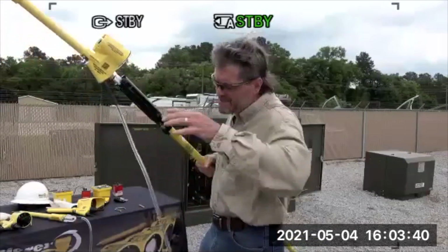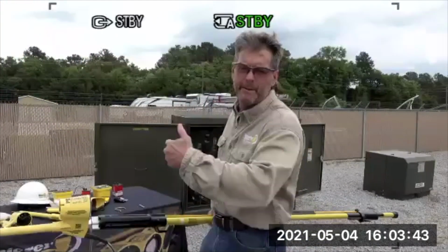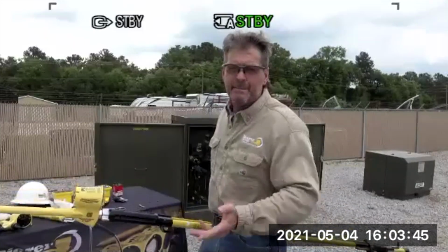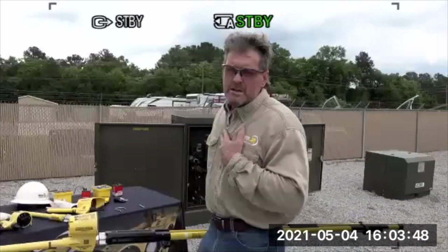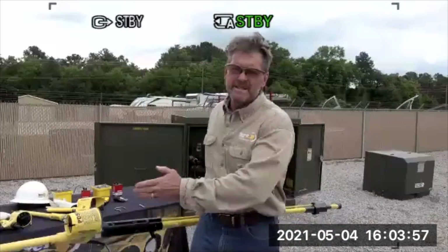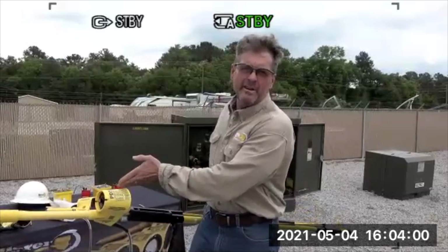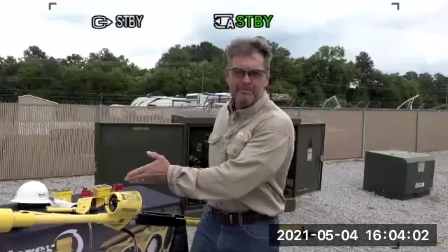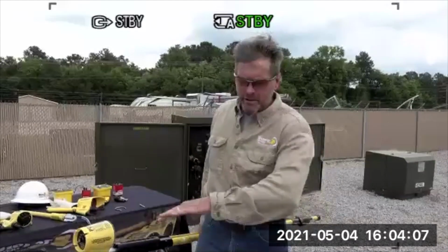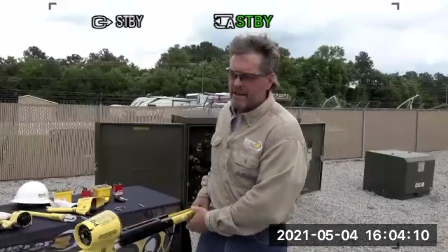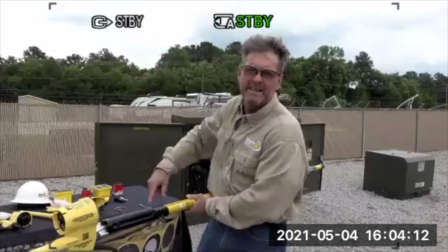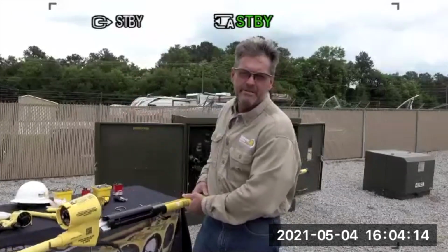When that happened, they just dropped everything and went running, screaming like girls, and I can say that because they actually told me that. So they sent pictures to us saying, hey, your tools suck, your tools are no good, they're dangerous. And sure enough, you can see exactly where that meter head was on that hot bus. It looked like one of those World War II movies, planes dropping a bomb on the ground, a big old crater. That paint was just all cratered up on that side of the substation.